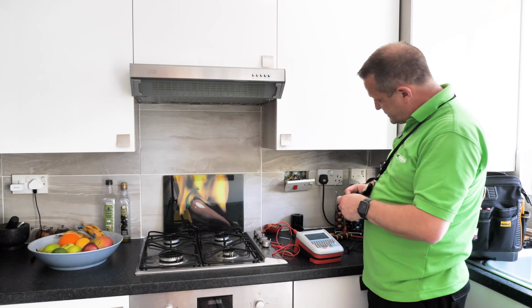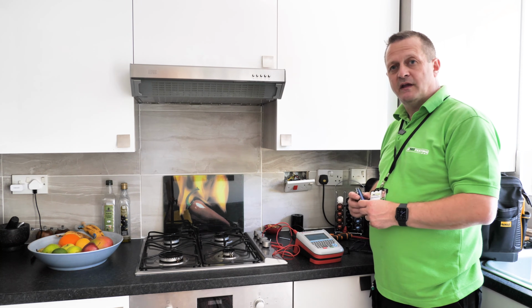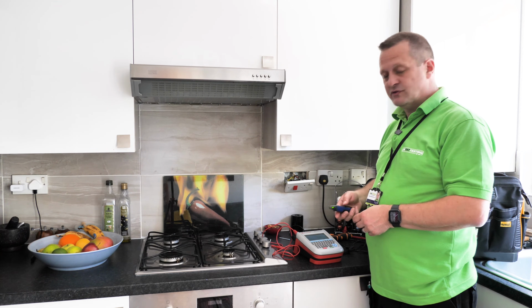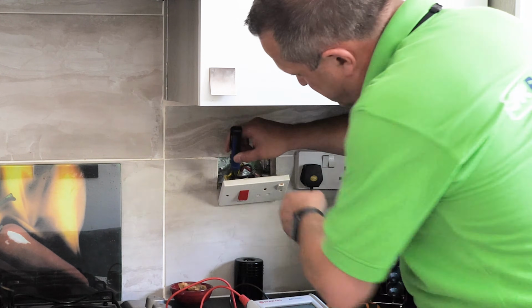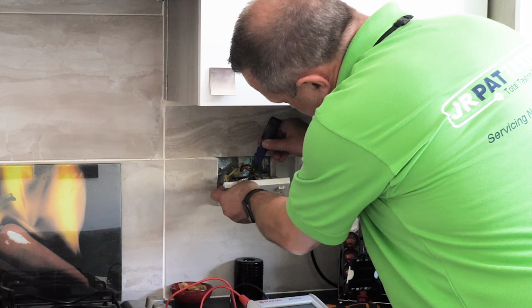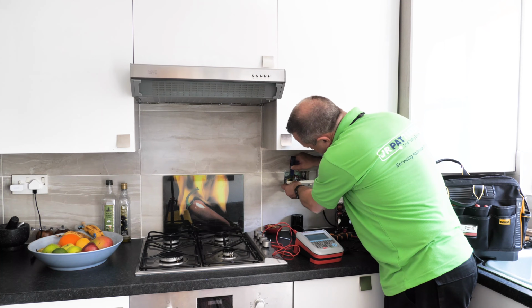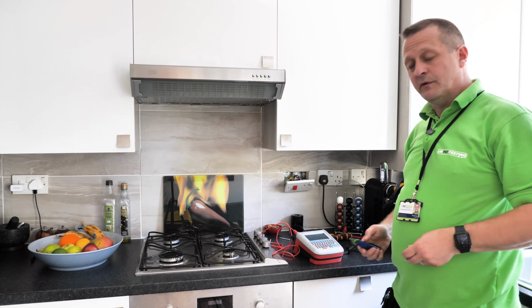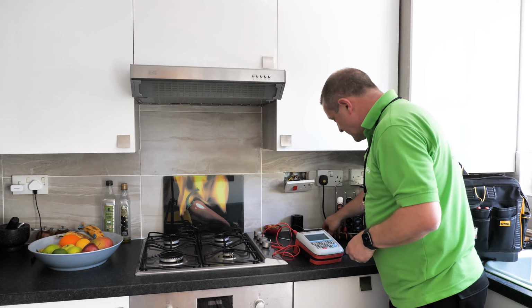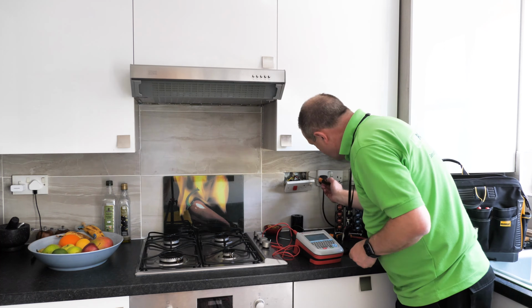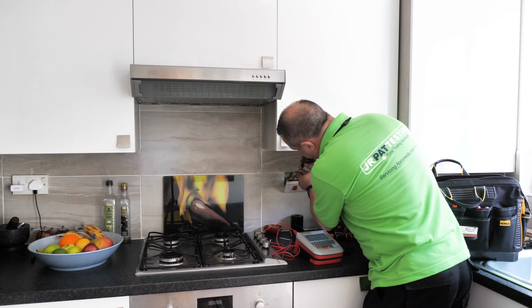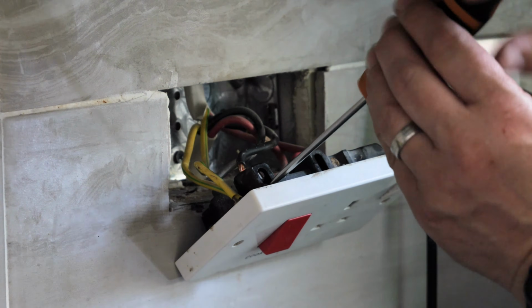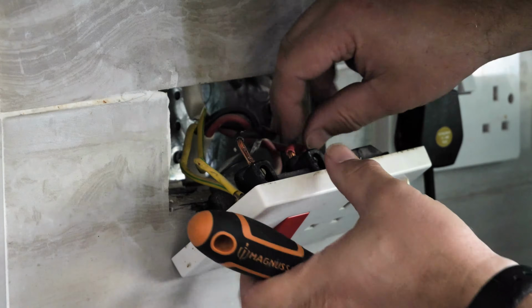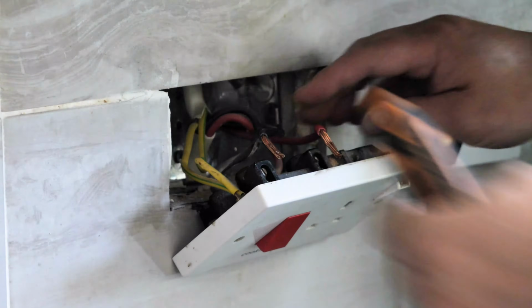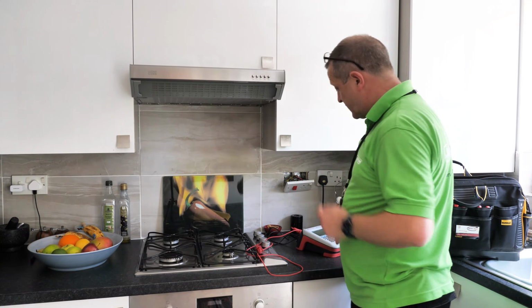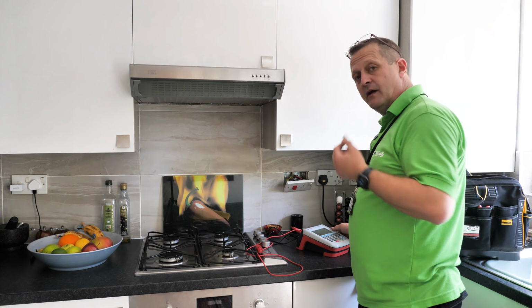Okay, so now we've opened up the socket, we need to make doubly sure that it is no longer live. Using a quick electrical tester, we're going to test against the earth, the neutral and the live cables, just to make sure that we're satisfied that there's no current going through. The next thing we need to do is to disconnect the live and the neutral from the socket. Right, so now that we've exposed the socket, we're going to get on with actually conducting the test.